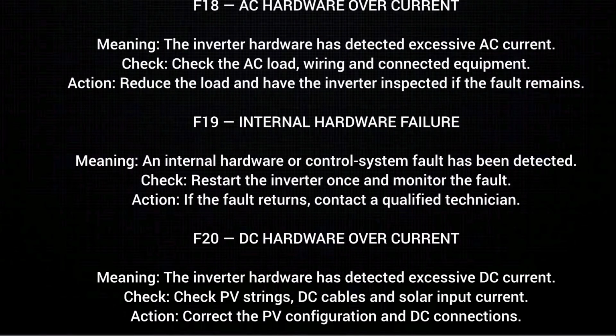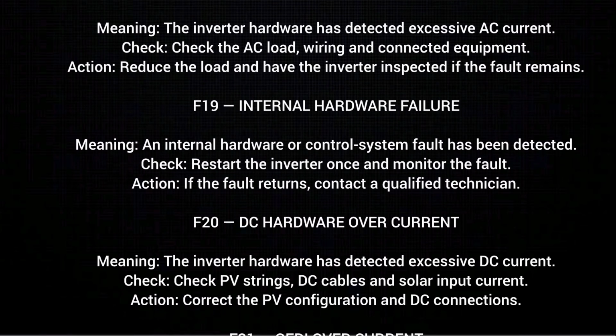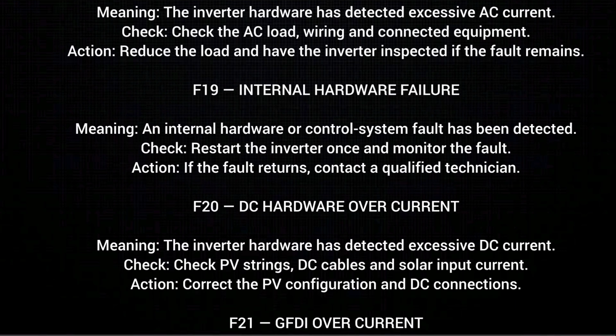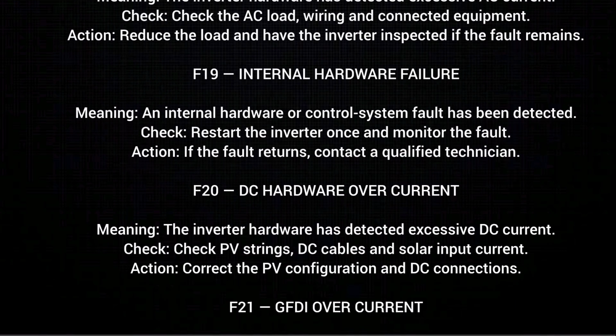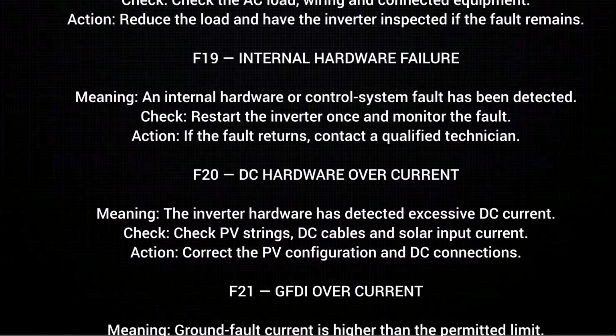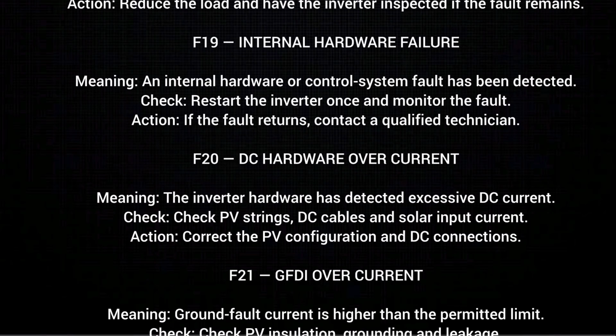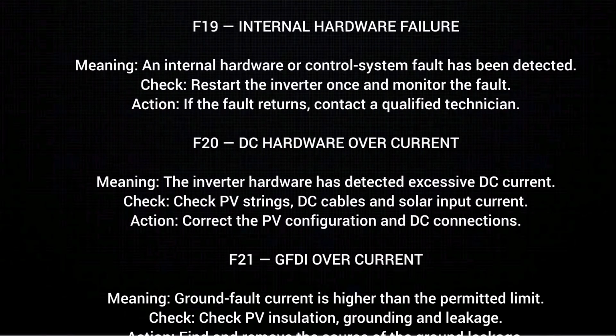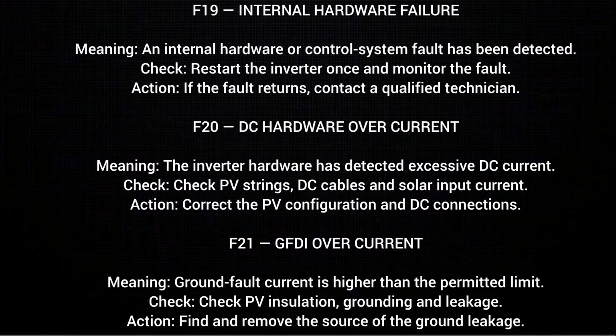F19 Internal hardware failure, meaning an internal hardware or control system fault has been detected. Check. Restart the inverter once and monitor the fault. Action. If the fault remains, contact a qualified technician.